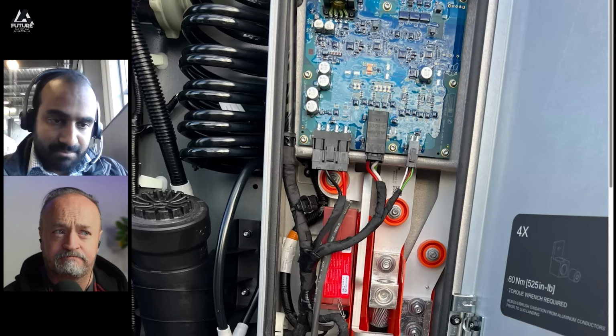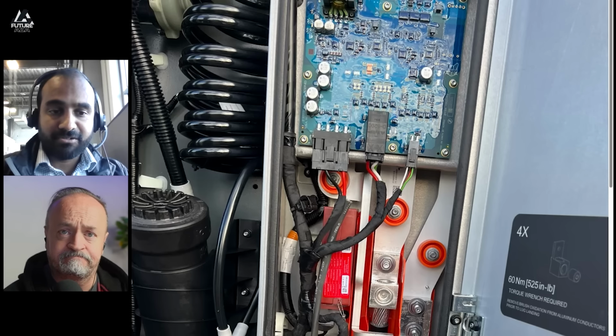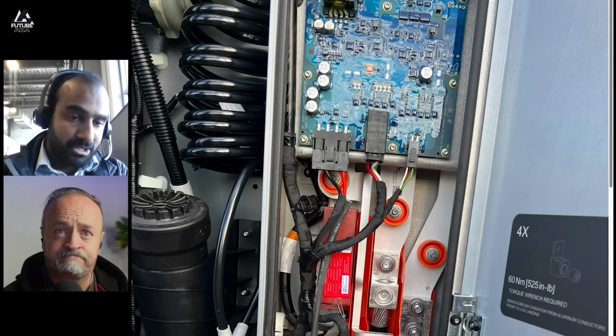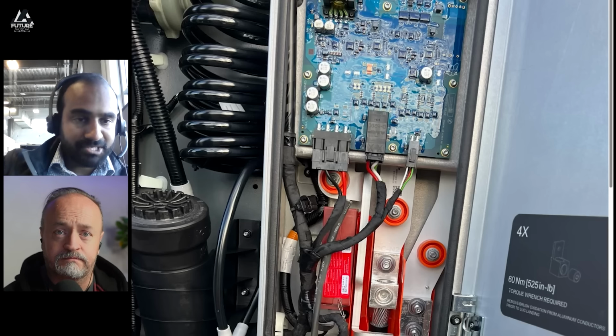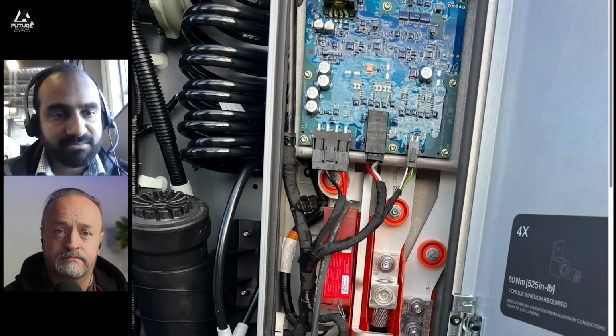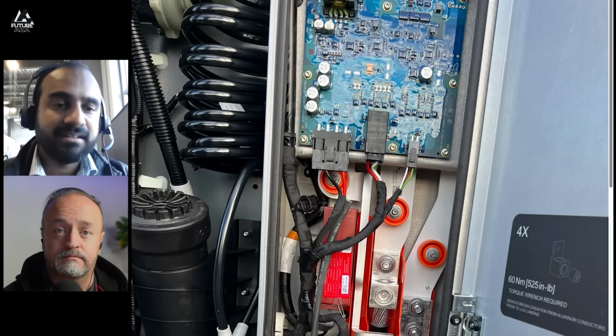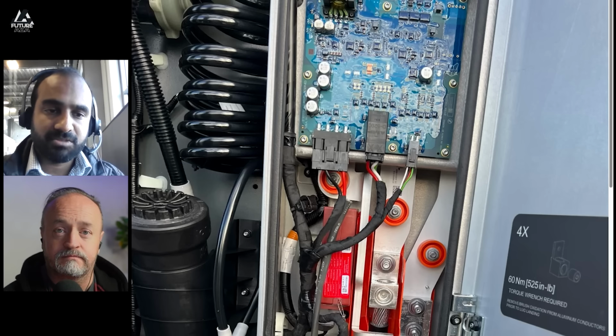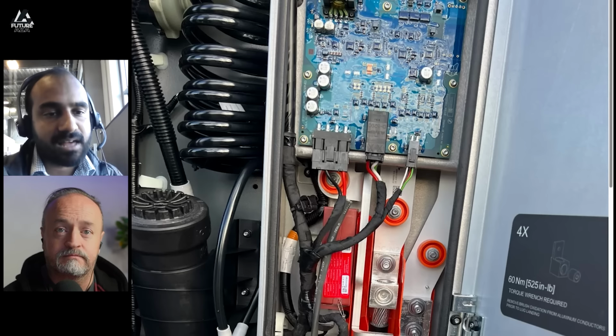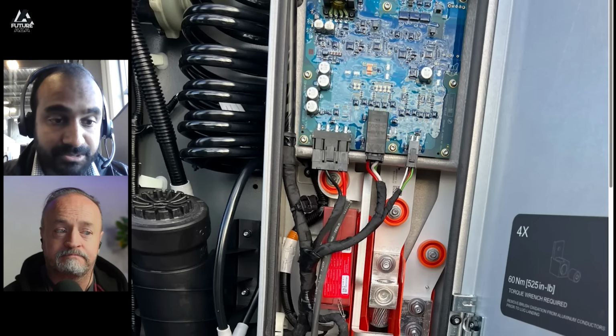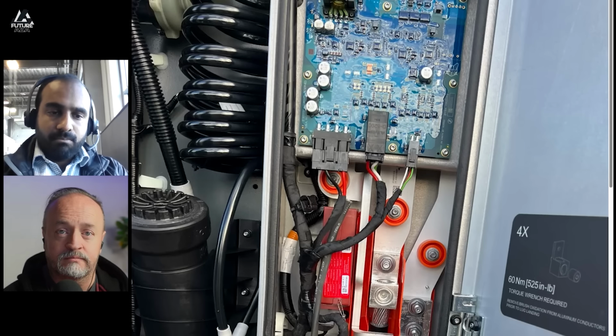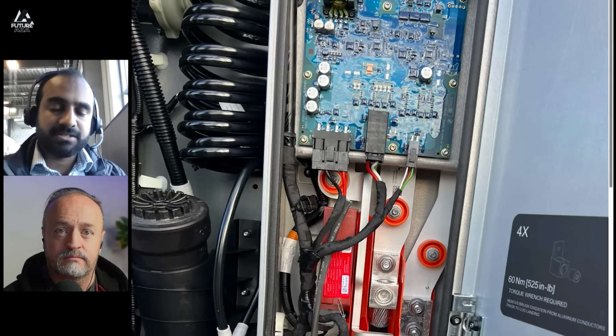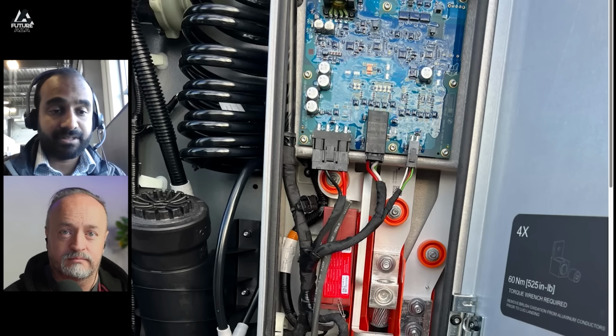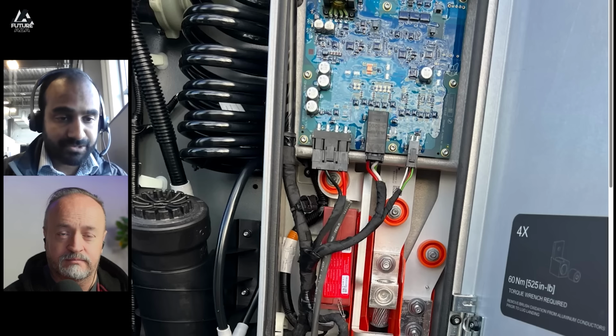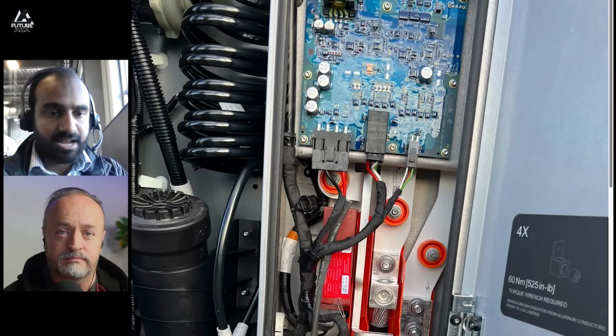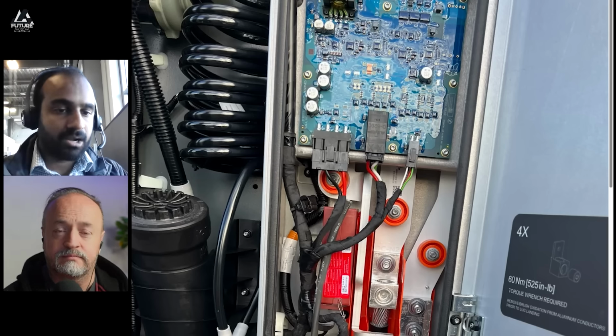Not all the heat is generated in the same place, right? So if you have a power cabinet and the power conversion is occurring in a separate location, then some of the heat being generated is actually happening not in this dispenser, but 25 feet away in a giant cabinet where you have access to more airflow, things like that you can use to help dissipate some of that heat. So generally speaking, a decent fraction - and it can really depend on the system - of the heat is being generated by power conversion, so in this case, the dispenser doesn't have to deal with all of the heat that is being generated in the system.